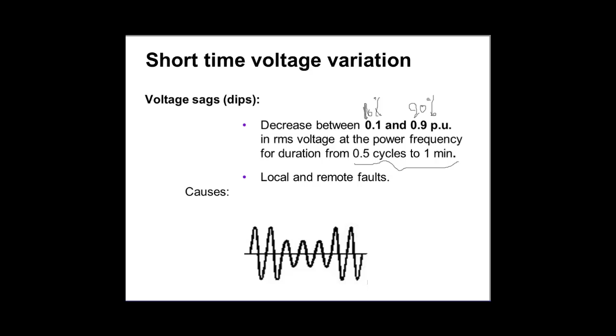If it is a very, very short period of time where you have that voltage drop, a voltage drop for a very, very short period of time is what we call the voltage sag or dip. That drop could be 10%, could be 20%, could be 80%, could be 90%, and that is the meaning of the voltage sag. It is caused by local and remote faults. Very, very bad faults. Even if it is 10 milliseconds, 20 milliseconds, you think, oh, it was nothing, mate, it was just half a millisecond. Well, whatever. Yes, you think it was very short, but it damaged a lot of things. So that's the meaning of voltage sag or dip.